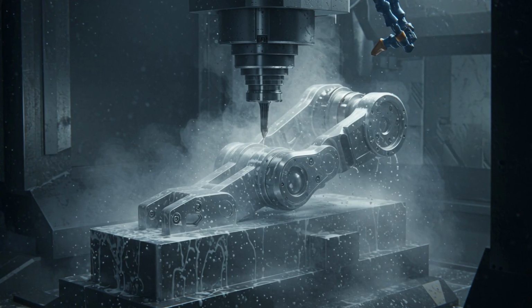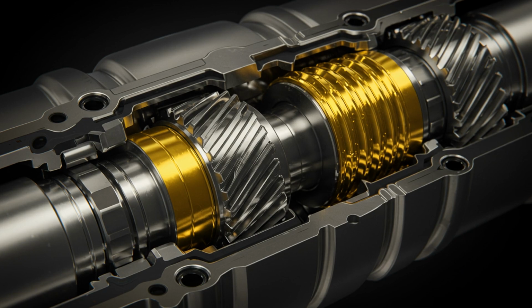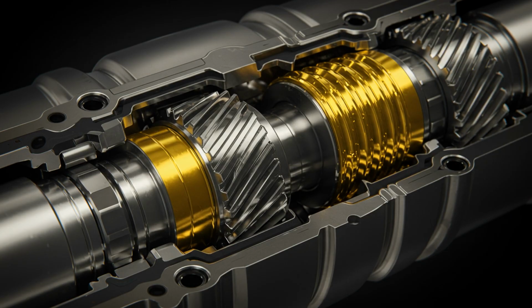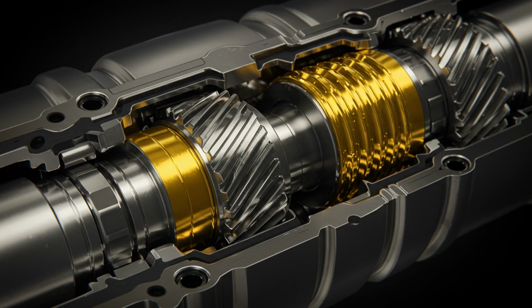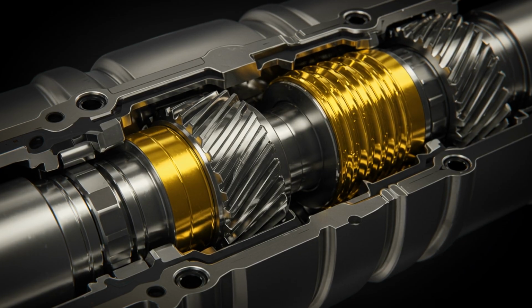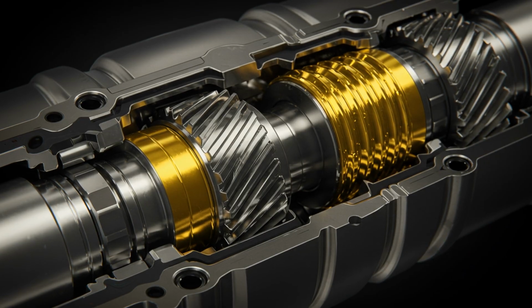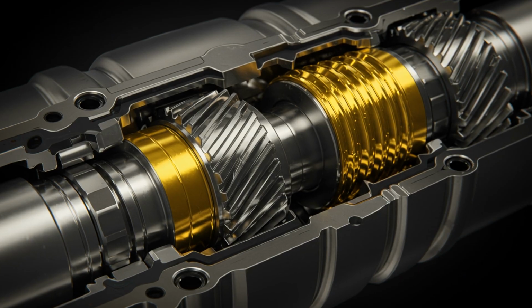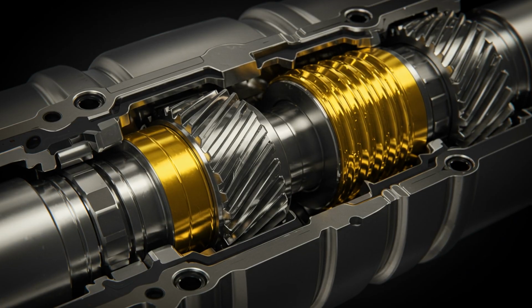How does a robot move with such fluid, jitter-free precision? The secret lies in the gearbox, specifically the harmonic drive. Standard gears have backlash, a tiny gap between teeth that causes a wobble. In surgery, backlash is unacceptable. A harmonic drive uses a flexible spline and an elliptical wave generator to create a massive gear reduction in a tiny space with zero backlash. As the motor spins at high speeds, the harmonic drive translates that into slow, incredibly powerful, and perfectly smooth movement.